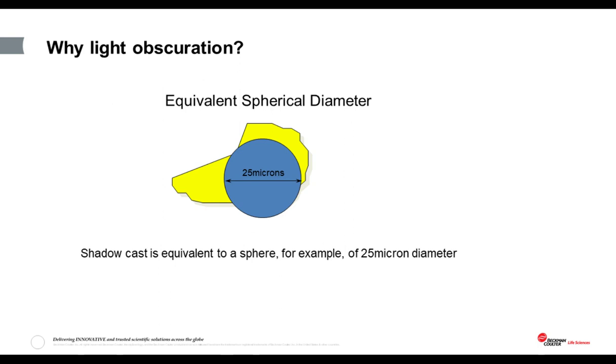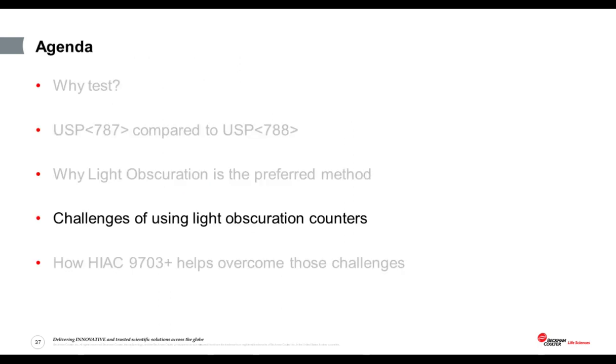Now, the attraction of this method is that the counter can be calibrated using certified traceable calibration beads of a known size. Now, these beads will obscure a fixed or certain amount of light, and now any particle, however irregular shaped it is, which obscures the same amount of light as the calibration beads, can be said to have an equivalent spherical diameter as the calibration beads. Thus, irregular shaped contaminating particles may be sized according to certified reference standards, and no matter what their shape, particles that obscure the same amount of light will be reported as being the same equivalent spherical diameter. Now, this helps almost eliminate the impact of subjectivity and human error from the measurement.